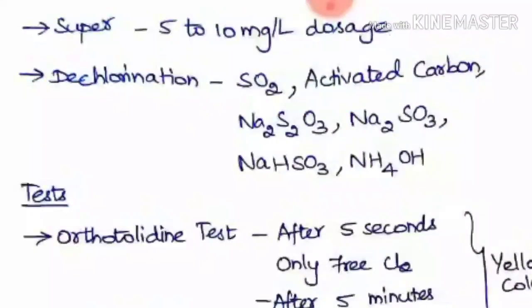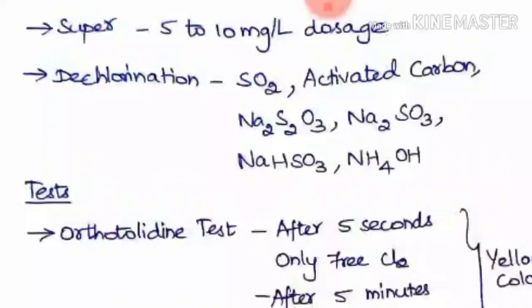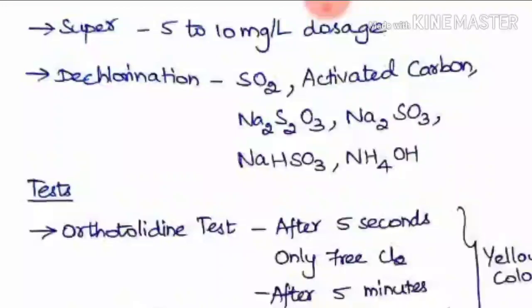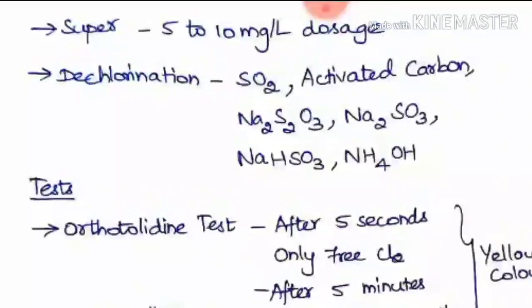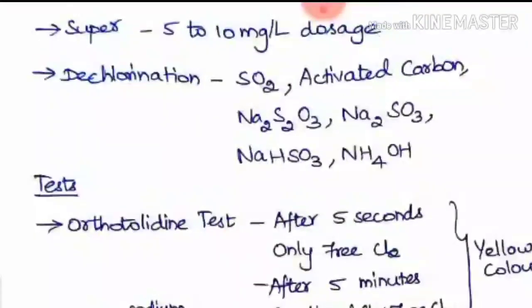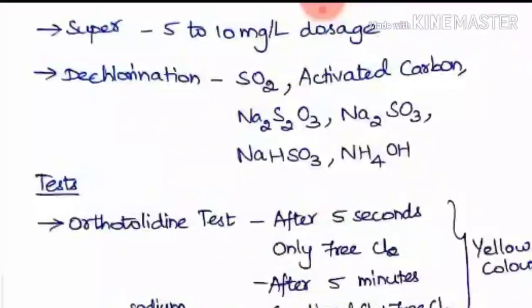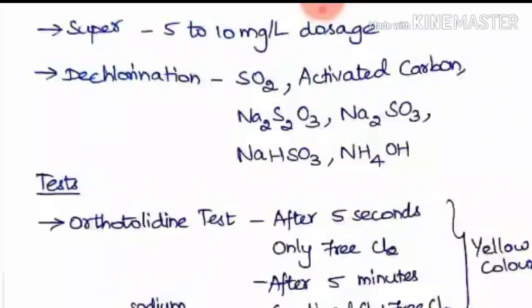Super chlorination uses a high dosage of 5 to 10 mg/L and is used when epidemic diseases have broken out or in very contaminated water sites. De-chlorination is performed when the residual chlorine becomes too high before sending water to the distribution system. It can be achieved by adding sulfur dioxide gas, activated carbon, sodium thiosulphate, sodium sulfite, sodium bisulfite, or ammonia in the form of NH₄OH.